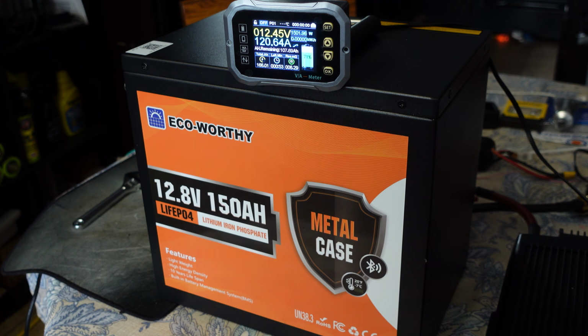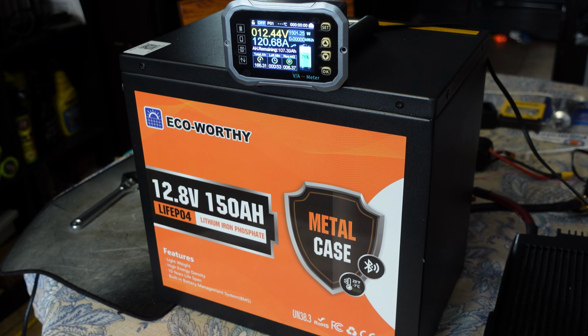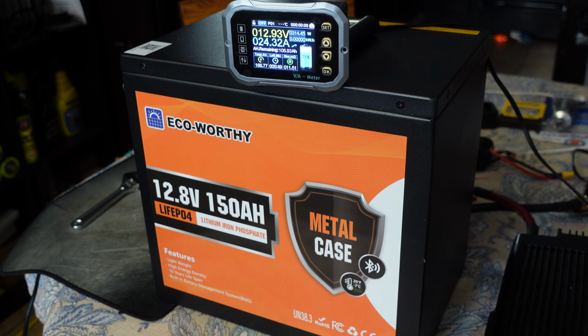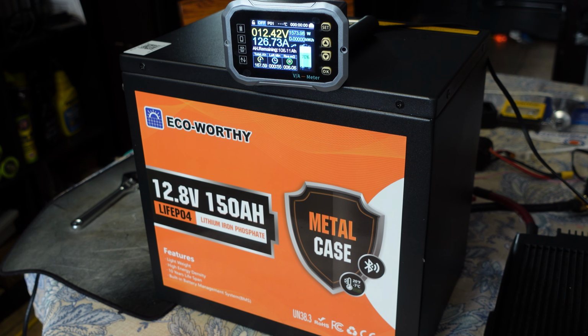Okay, no problem at 120. Now we're gonna crank it up to see if we can get it to hit the overcurrent protection in the BMS. So I'm gonna go ahead and crank the current up a little bit more. It says it'll do 130 amps for 10 seconds. 126 amps, let's see if we can get to 130.